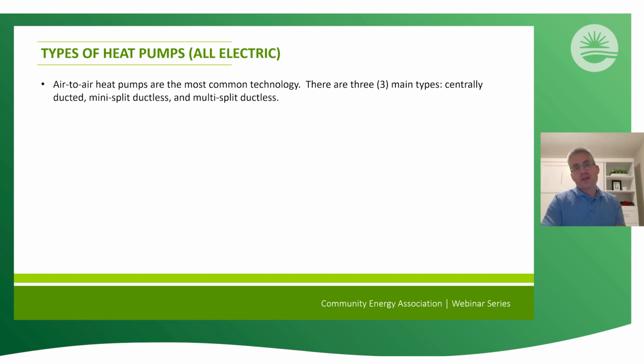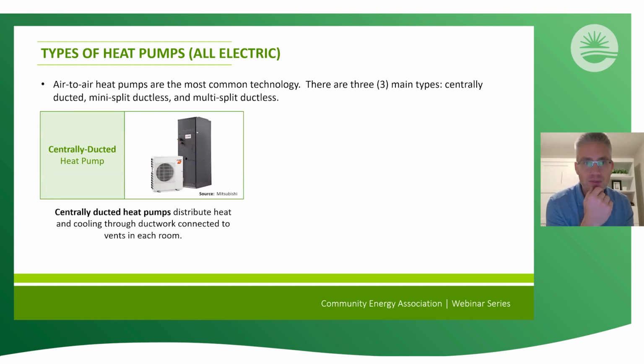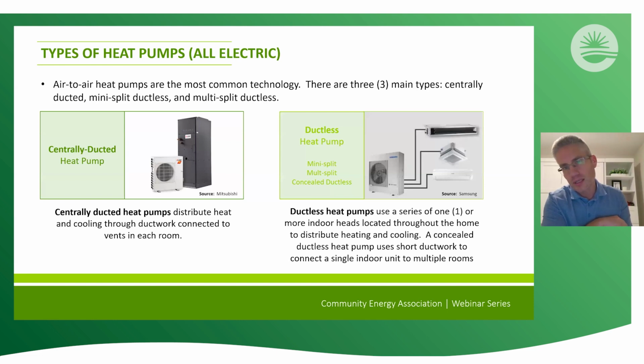In terms of types of heat pumps, we'll start with the all electric ones. Air to air heat pumps are the most common technology, and there are really 3 types. The first is centrally ducted heat pumps, where the heat pump distributes heating and cooling through ductwork connected to vents and grills inside your house. The second type is a ductless heat pump, which may be a mini split, multi-split, or even a concealed ductless configuration. Ductless units use 1 or more indoor heads located in the home to distribute the heating and cooling. A concealed ductless heat pump uses short ductwork runs that connect a single indoor unit to multiple rooms in your house.